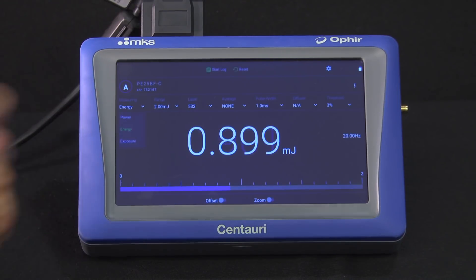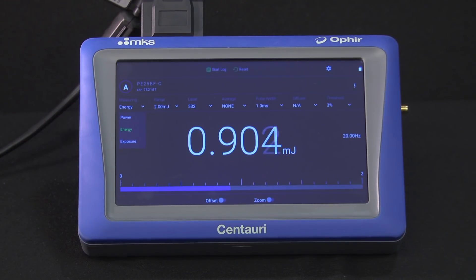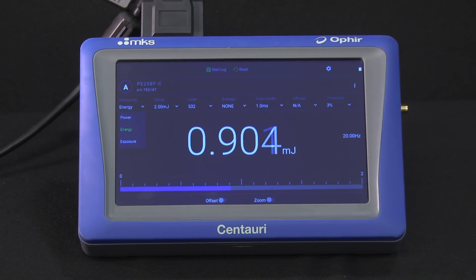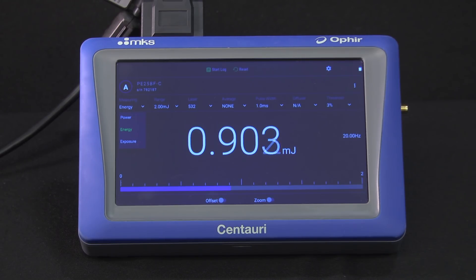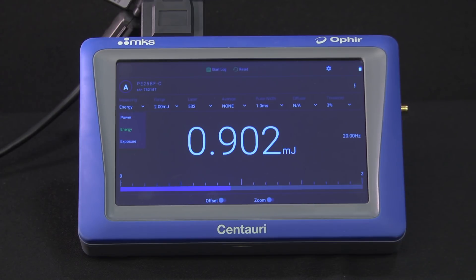Here we set the measurement type. For any beam whose energy per pulse the pyro sensor can measure, it can also measure the beam's average power. Exposure measures the total accumulated energy over the user-controlled duration of the measurement.